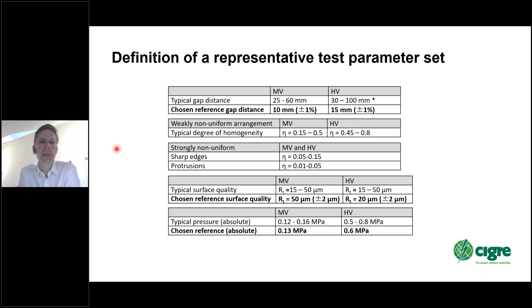Of course, the gap distances, ideally, we would have loved to measure in larger gap distances, so more towards industrial standards or what is used in practice. But because we also wanted to perform some of these measurements and the participating test laboratories were limited in voltage, or many of them were limited in maximum voltage application, we had to decrease this gap distance. But the rest was definitely within the range of practical applications which were used for medium and high voltage GIS equipment.